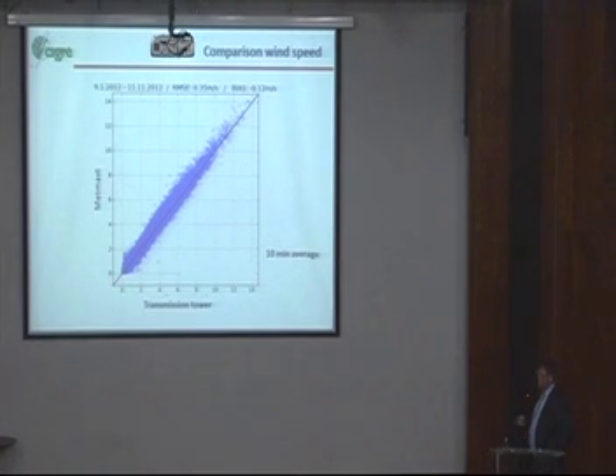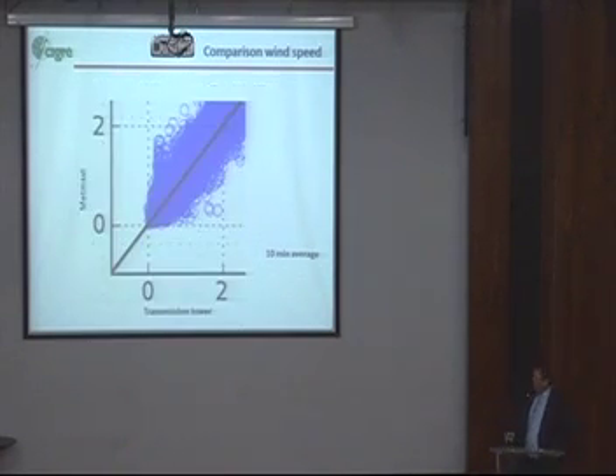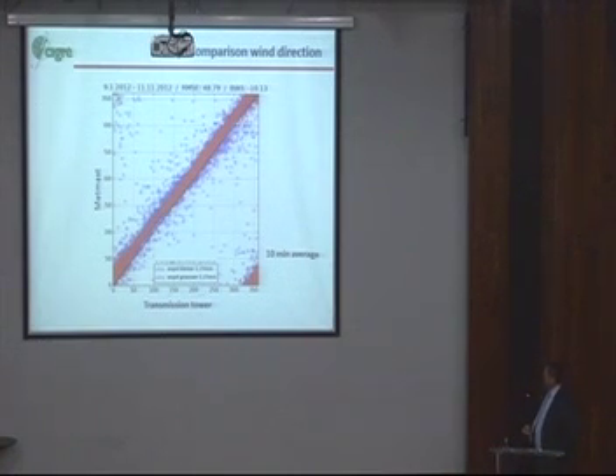If you look at dynamic line rating, you don't care about the high wind speeds, because this resolves all problems. What is critical for you is these low wind speeds down here. And when I zoom in, you can see that 1 meter per second wind speed on one side causes a wind speed of roughly 0 to 2 meters per second on the other side, which is 200 meters away. So within 200 meters, you can have a huge variation in wind speed. And the other parameter is wind direction. If you compare the direction here with here, you can see an offset of about 25 degrees. That means that within 200 meters, the direction changes by 25 degrees. And all these values you have seen are 10-minute average values already.